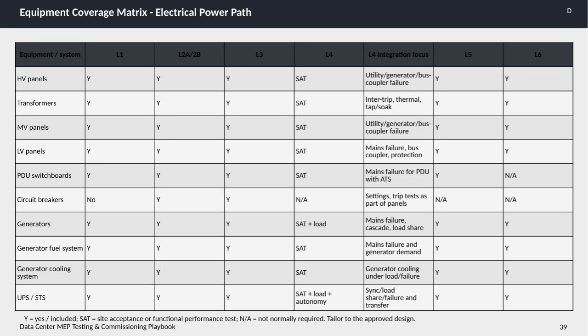Here we have the equipment coverage matrix for the electrical power path, which outlines the testing and commissioning requirements across different levels for various electrical components in a data center. Looking at the matrix, the columns represent different testing levels, from L1 through L6, with specific integration focuses at L4. The rows list key equipment such as high voltage panels, transformers, medium and low voltage panels, power distribution unit switchboards, circuit breakers, generators, and their auxiliary systems like fuel and cooling.